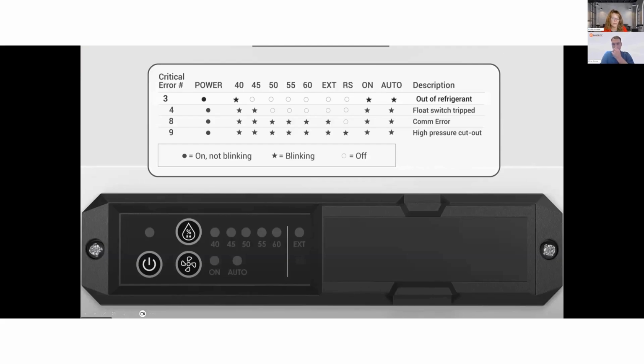And we've incorporated error codes into these units as well to be able to efficiently and quickly diagnose if there is an issue. And these are all errors that are going to be critical, meaning that the dehumidifier is not functioning and removing water. And so we're not going to send out error codes for minor things that aren't going to affect the dehumidifier, to help prevent callbacks to the field. So you can see here what it'll be is a series of lights that'll flash. And we've got these in our manuals and also on the website, so you'll be able to quickly know what's going on with those.